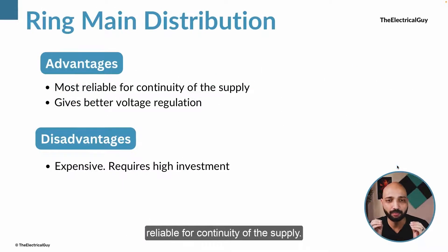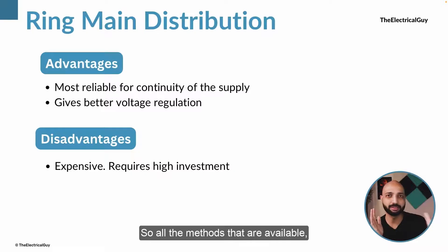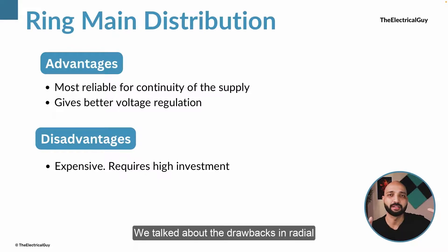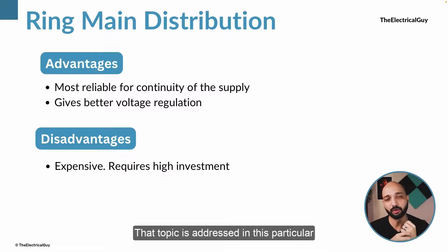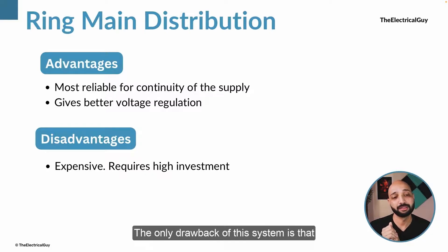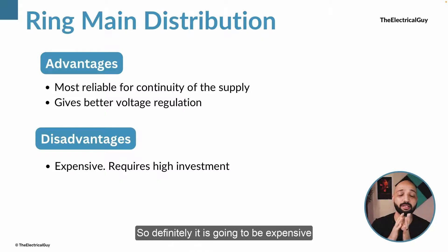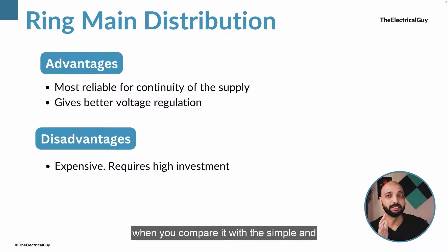The advantages of ring main distribution are that it is the most reliable method for continuity of supply and provides better voltage regulation compared to radial distribution. The only drawback is that it is very expensive and requires high maintenance, since it needs parallel feeders and ring main units — making it significantly more costly than the simple radial distribution.